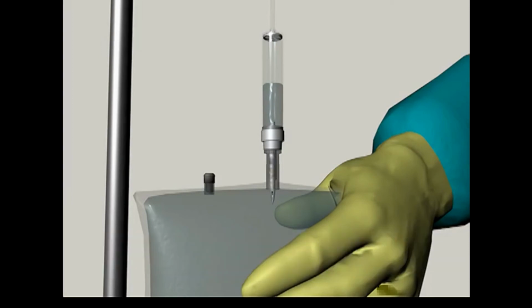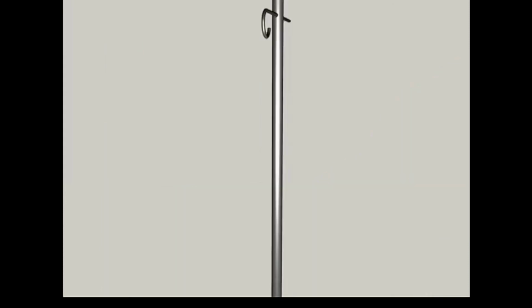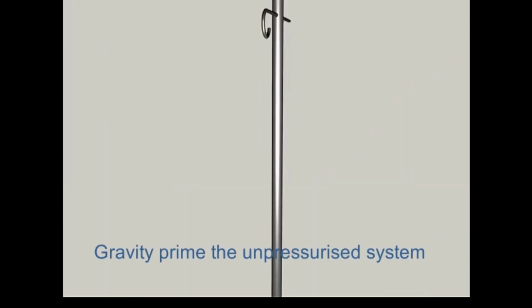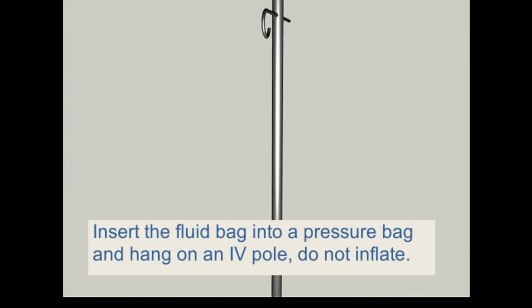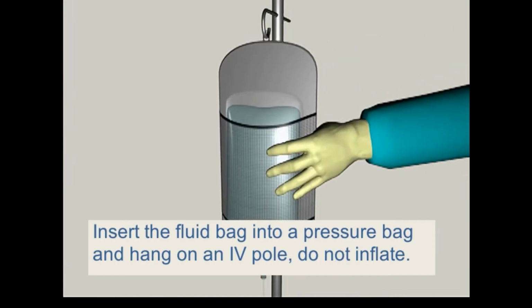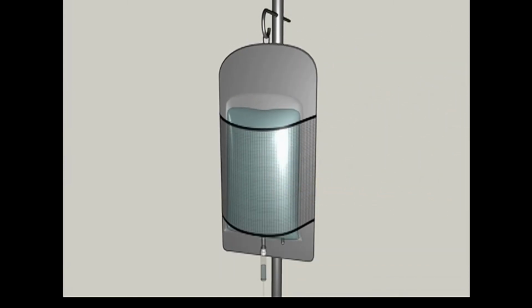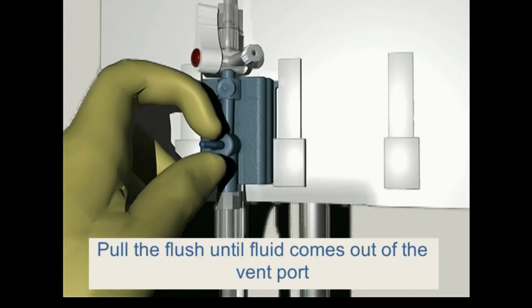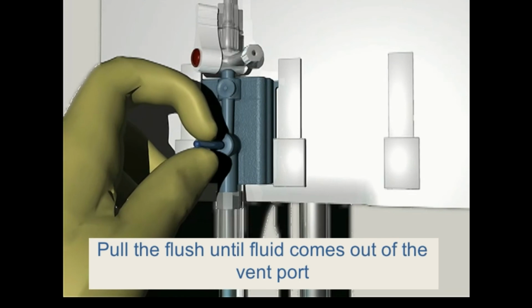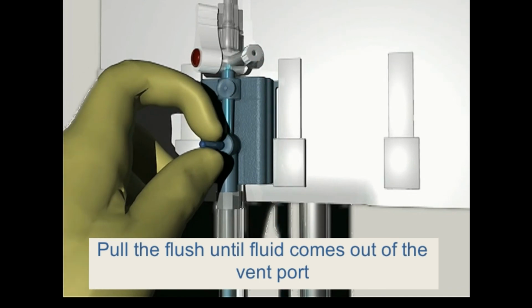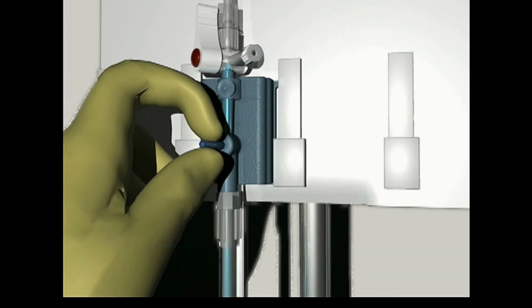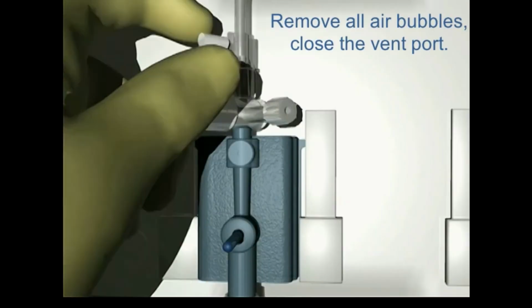Step 4. Gravity prime the TrueWave system. Insert the IV bag into a pressure infuser bag and hang on an IV pole. Do not inflate. Pull the snap tab flush device to deliver the flush solution through the TrueWave transducer and out through the vent port's vented cap. Remove all air bubbles.